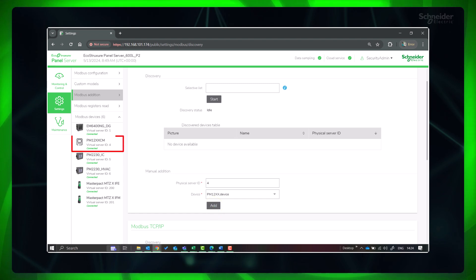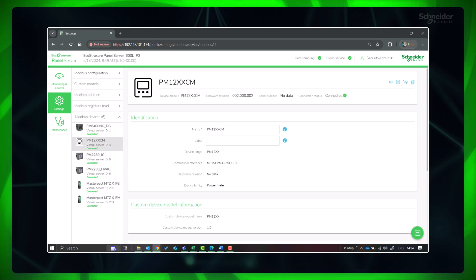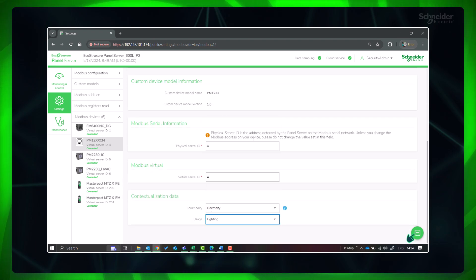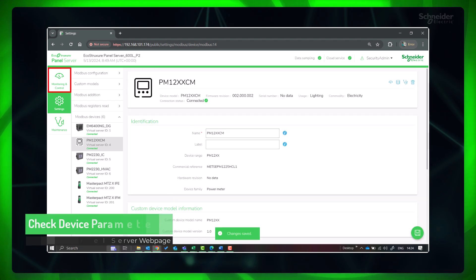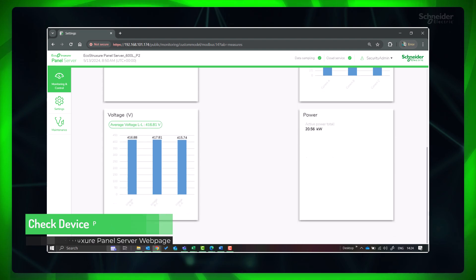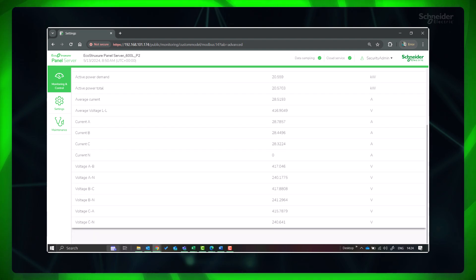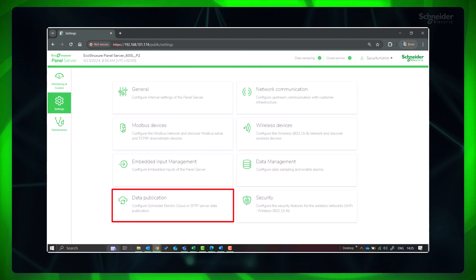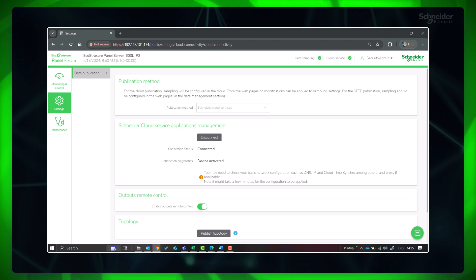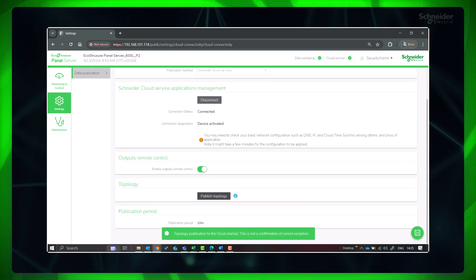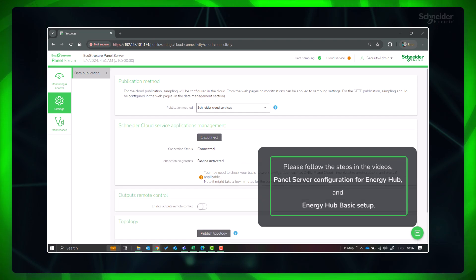The device is added to Panel Server. Provide the respective contextualization data. Go to Monitoring and Control and select the device to check the parameters — all parameters are coming correctly. If the Panel Server is already connected to Energy Hub, go to Data Publication and republish the topology.